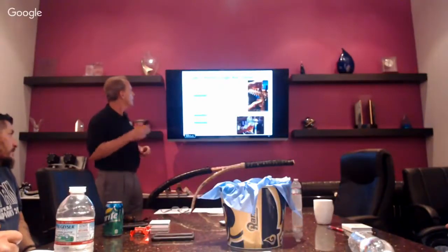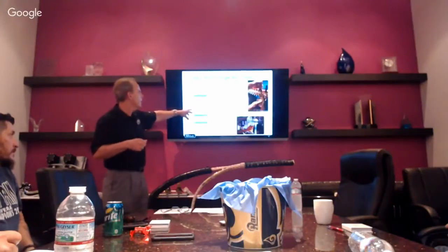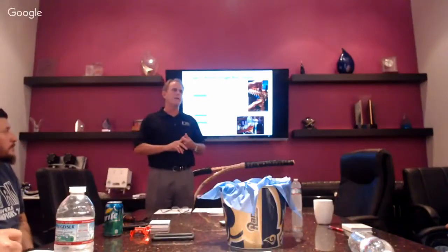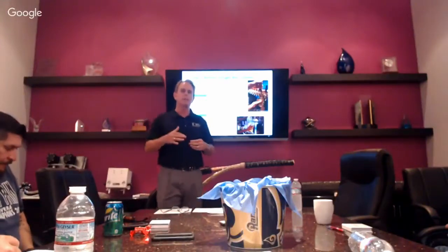Okay, so the high pressure. Go back. The blended systems have two areas of concern. One, they max out at about 300 feet. And again, it all has to do with pressures: how high it is, how warm it is. The rule of thumb is about 300 feet. If it's a high pressure situation where you use a lot of pressure, it might only be 200 feet.